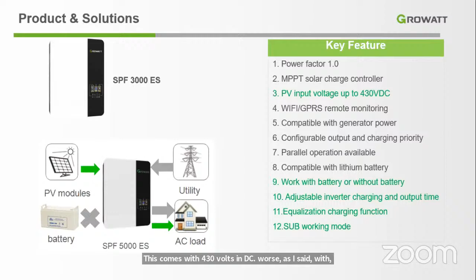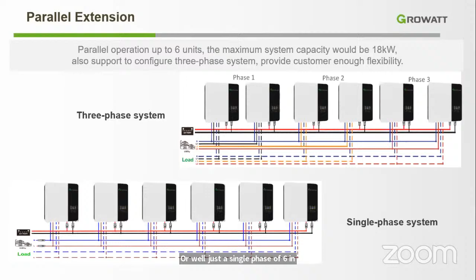Well, this can be connected the same as the other one, up to 6 inverters. You can connect 2 per phase for a 3-phase system, or use a single phase of 6 inverters, for a maximum of 18 kilowatts of power at the same time.